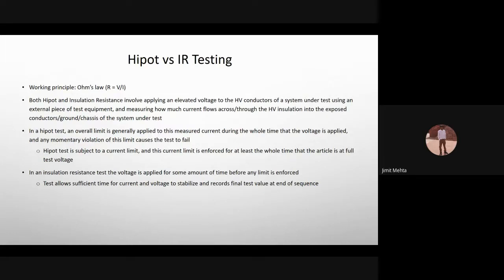People often mistakenly interchange the terms HiPot and insulation resistance testing, but there's a fundamental difference. HiPot testing involves applying a voltage and measuring the current throughout the entire testing period—you don't allow stabilization to occur on the device under test. The reason is that when something arcs or there's an electrical current leakage, it creates a carbon deposition layer, which can insulate it for an initial moment, allowing it to pass your testing if you aren't monitoring throughout the period.